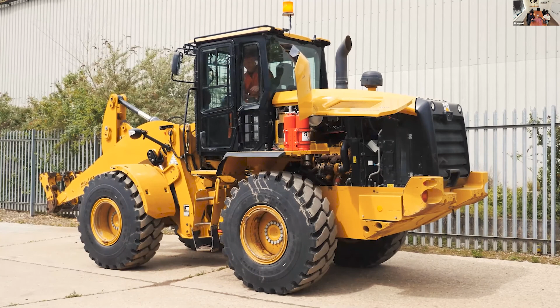You can see that the dry chemical fills the engine bay and the areas underneath. And what you can see now is the wet chemical cooling the manifold and turbochargers. That was a hot engine, and you can see that now the steam has subsided, and the components you see, the turbocharger exhaust, are all cooled below a level that would cause ignition of flammable fluids.